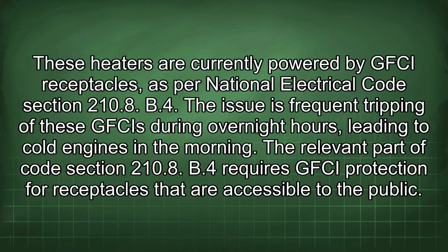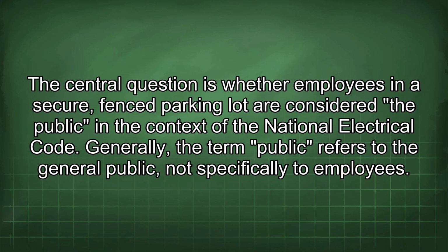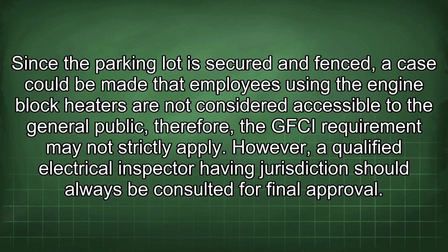The relevant part of Code Section 210.8 B4 requires GFCI protection for receptacles that are accessible to the public. The central question is whether employees in a secure, fenced parking lot are considered the public in the context of the National Electrical Code. Generally, the term public refers to the general public, not specifically to employees. Since the parking lot is secured and fenced, a case could be made that employees using the engine block heaters are not considered accessible to the general public. Therefore, the GFCI requirement may not strictly apply. However, a qualified electrical inspector having jurisdiction should always be consulted for final approval.